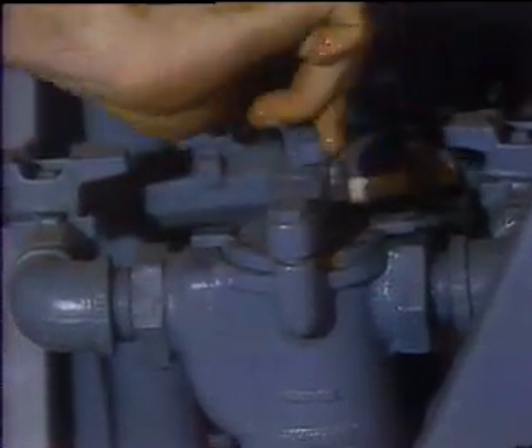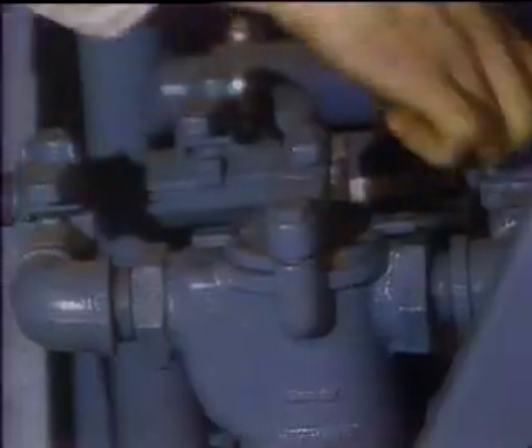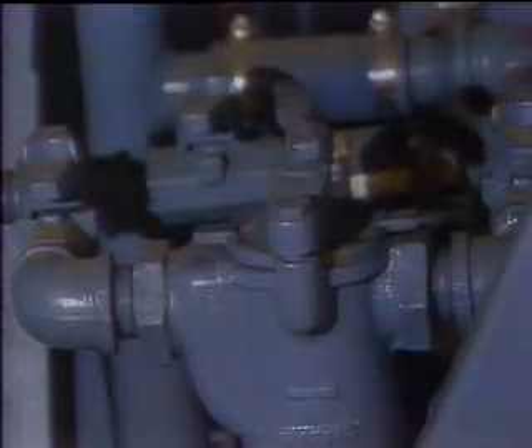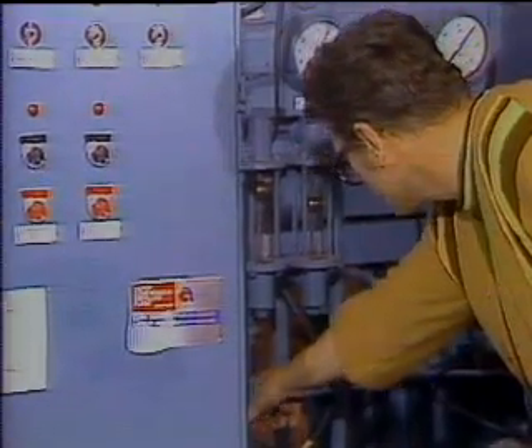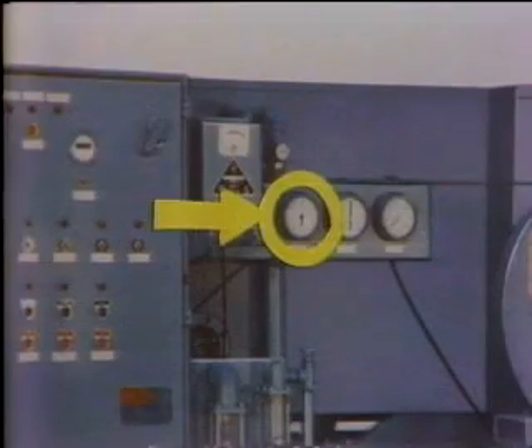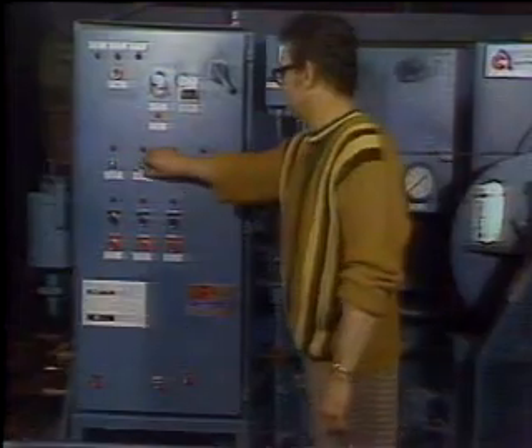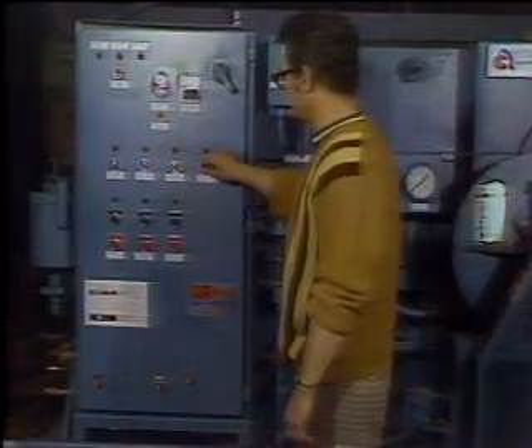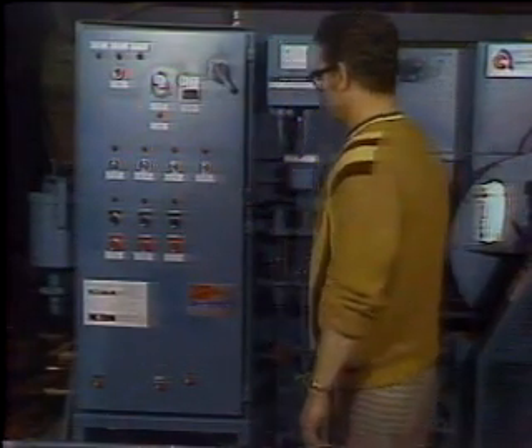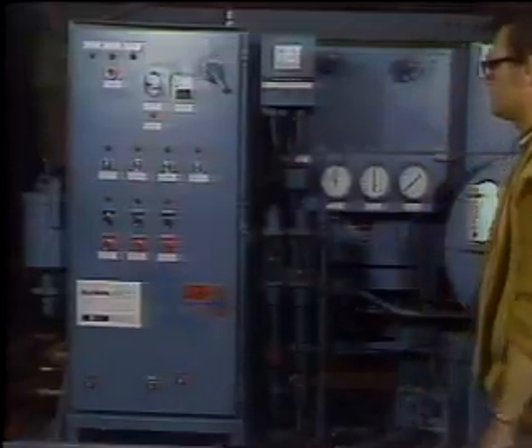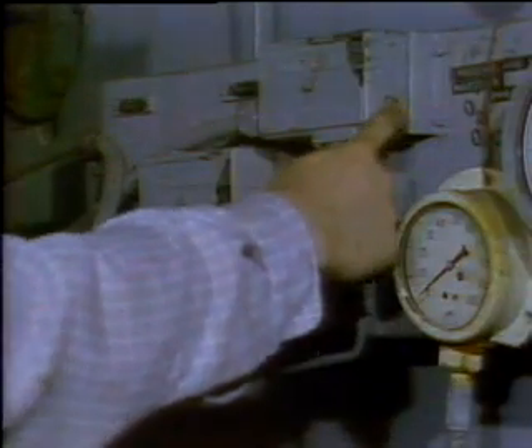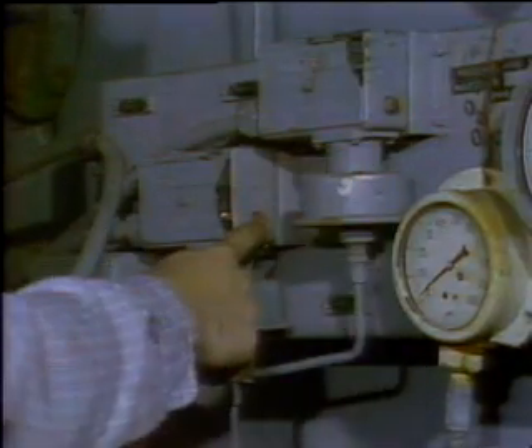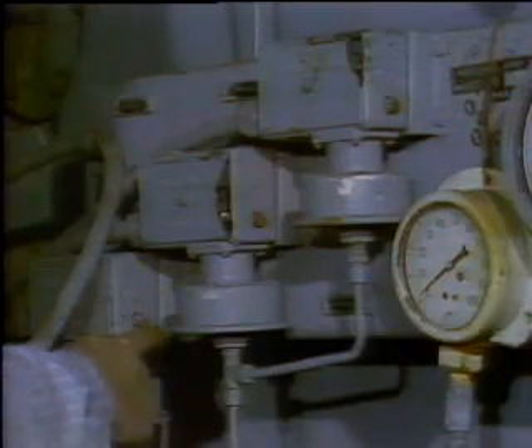Don't forget to put it back online after you've cleaned it. There are a couple other things to watch for while the unit is operating. Every now and then, check all flow rates to make sure that everything's running at the proper rates. If the compressor suction pressure begins to drop, turn the heaters back on manual until it comes back up to between 0.5 to 1.0 psig. You might have to readjust the automatic heater pressure switch if the pressure level won't stabilize. Check your manual for this.